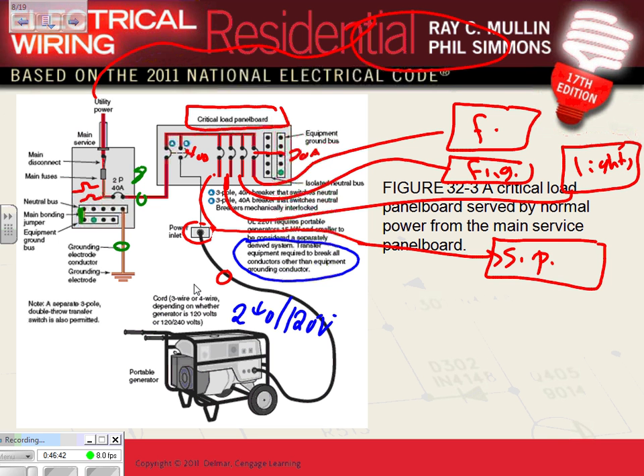And what they do, guys, for this one, they bond the neutral and the ground right in here. I'm going to draw this. They take the neutral and the ground, bond them right in here. I don't know if you guys can see that. And then they bring the hot, the neutral, and the ground, and it's bonded right inside the frame of a generator. That's why it's separately derived system. In the portable generators, they're considered separately derived system.